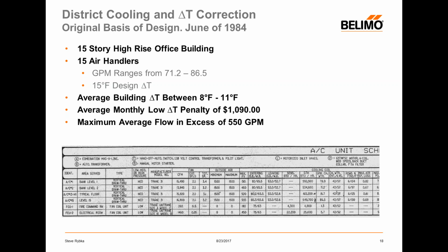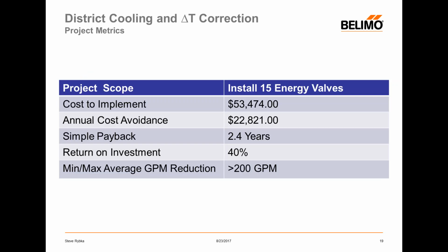So what did we do? We did something relatively simple. We installed 15 energy valves in this facility with an overall implementation cost of $53,474.